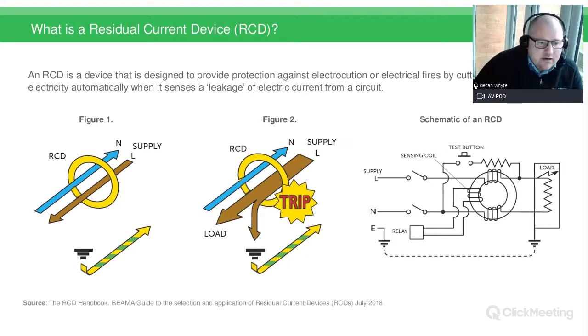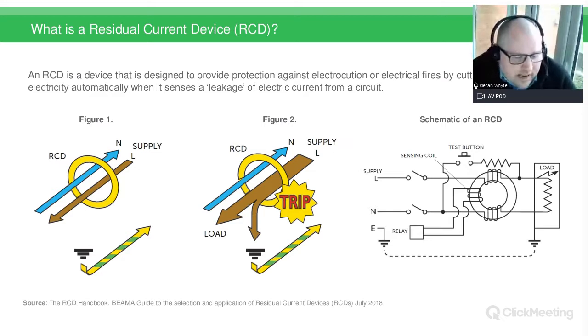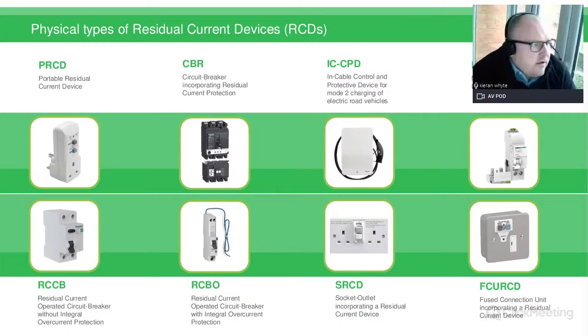So what is a residual current device? It monitors the current going out and returning from the circuit, and if those two values don't match, it operates a trip circuit at a certain threshold level and disconnects the supply. So it monitors the leakage to earth of current. Physical types of RCDs have probably changed over the years, so I'll talk you through some of the main ones we're seeing. Possibly one of the first things we saw maybe 15, 20 years ago was the PRCD, the portable residual current device, which was attached or sold as a plug-in device for electric lawnmowers outside in the garden. So that was really the first kind of consumer access to RCDs.